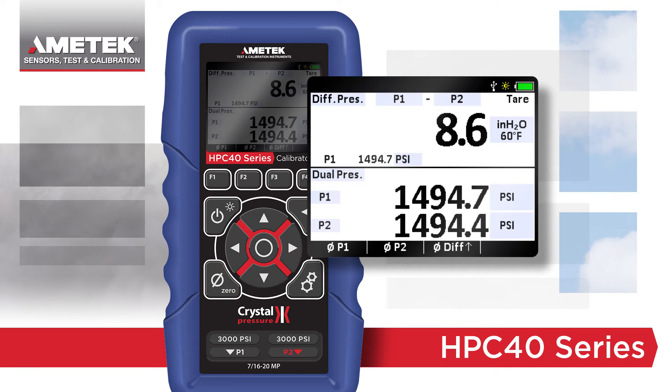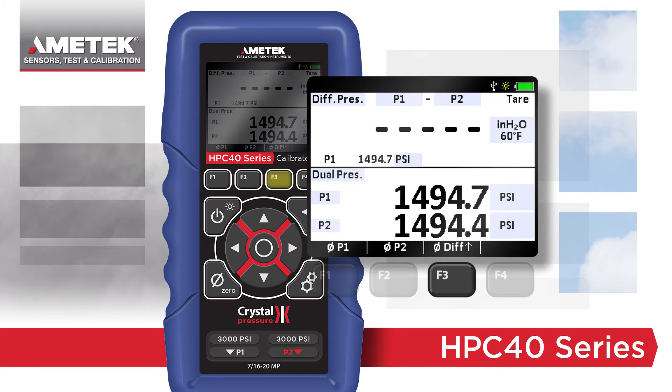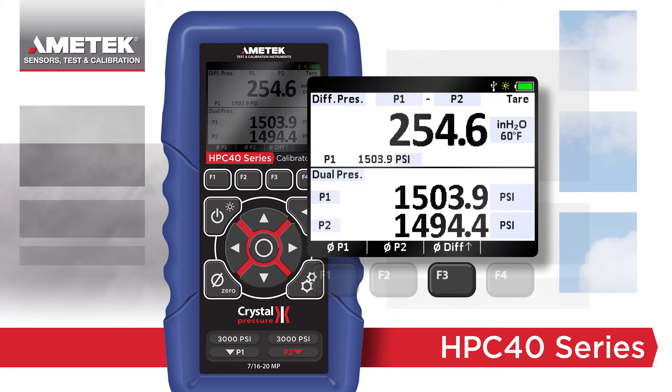In this example, both P1 and P2 are connected to the same pressure. A special tare DP mode allows you to remove this difference by pressing the differential function button. This increases the accuracy of your DP measurement. Because of the split display, both static pressures can also be viewed at the same time.